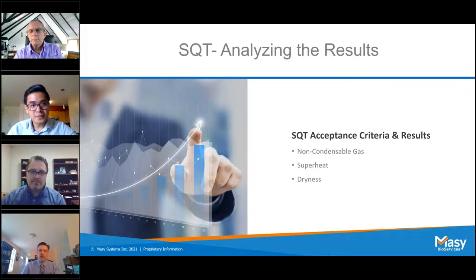And Tuan, would you be able to go over the analyzing of the results? Yes, I will be able to, Rob. To add on and reiterate to John and Sylvan's statements earlier about the test, we'll dive deep into the acceptance criteria and results of each steam quality test. The first one we'll go over is non-condensable gas testing. The idea behind the test is to analyze how much air or other gases is in your line, as Sylvan stated earlier. If there's too much gas or air in your steam line, then you may get false sterilization as they are poor sterilants. The acceptance criteria per EN285 for non-condensable gas testing is less than or equal to 3.5% by volume of non-condensable gases. So if you have 100 milliliters of condensate, then your non-condensable gases, your air or whatever, has to be 3.5 milliliters or less.